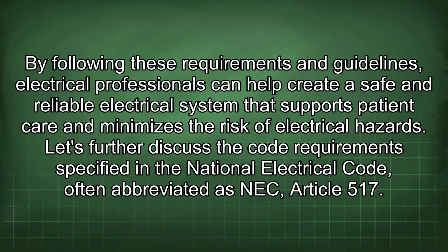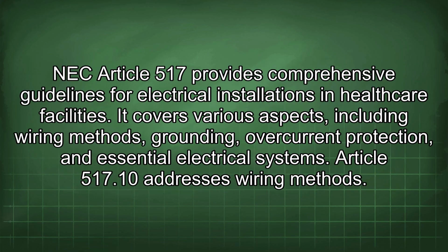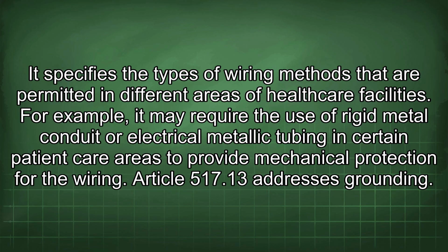Let's further discuss the code requirements specified in the National Electrical Code, often abbreviated as NEC Article 517. NEC Article 517 provides comprehensive guidelines for electrical installations in healthcare facilities. It covers various aspects, including wiring methods, grounding, overcurrent protection, and essential electrical systems. Article 517.10 addresses wiring methods. It specifies the types of wiring methods that are permitted in different areas of healthcare facilities. For example, it may require the use of rigid metal conduit or electrical metallic tubing in certain patient care areas to provide mechanical protection for the wiring.